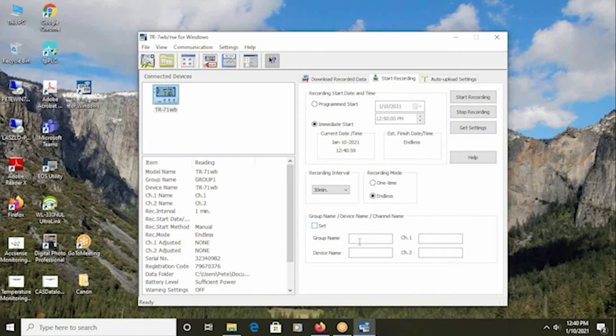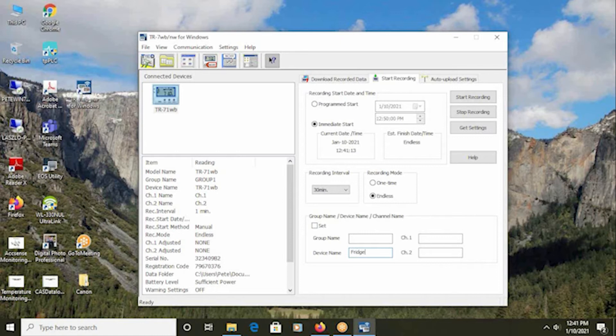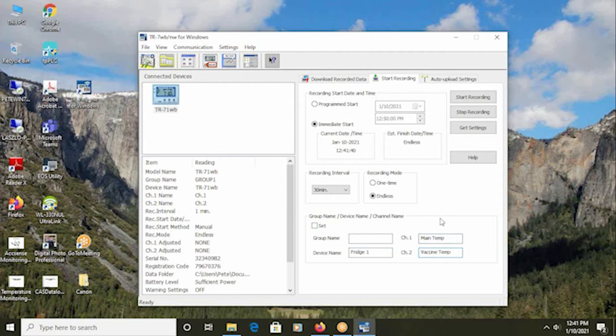You should also set up a group name. So if the logger is going to be organized into groups, lab number one, upstairs lab, whatever that may be, and a device name specific to this data logger. For this example, I'll name it fridge one. You can also assign a name for each of the two individual temperature channels available within the data logger. If you have separate areas in the freezer or refrigerator and are using both sensors in the same cavity, those can be named whatever is appropriate for your application. When you've completed this, click the start recording button.